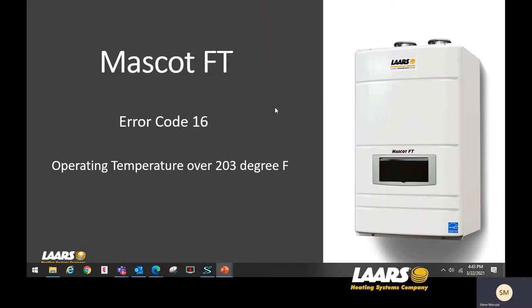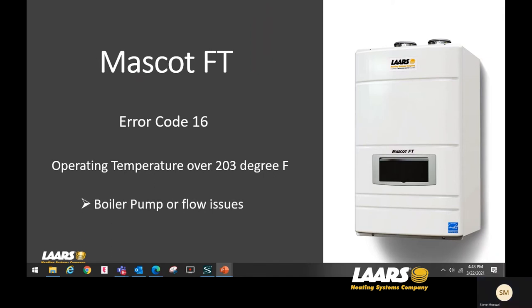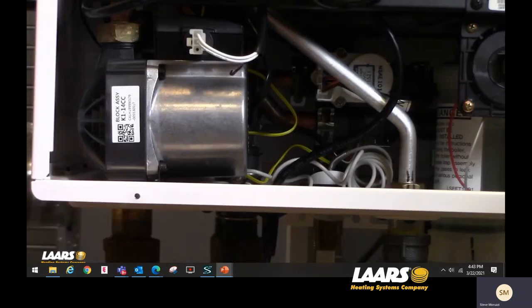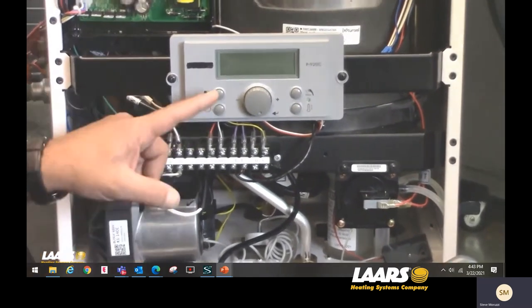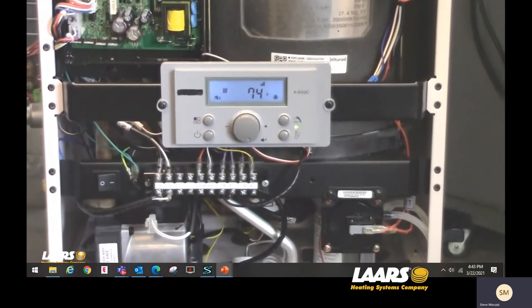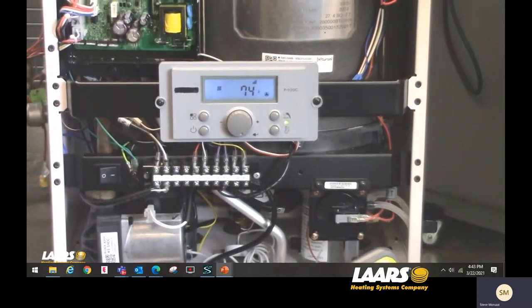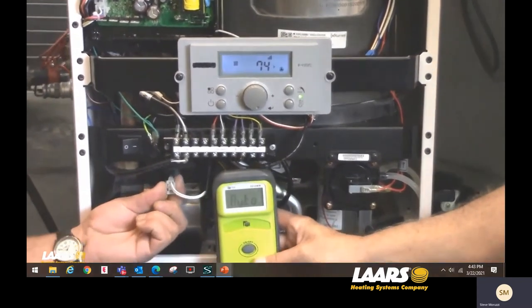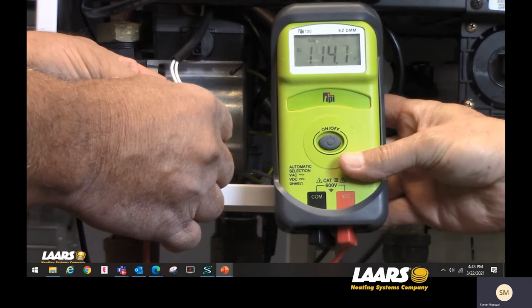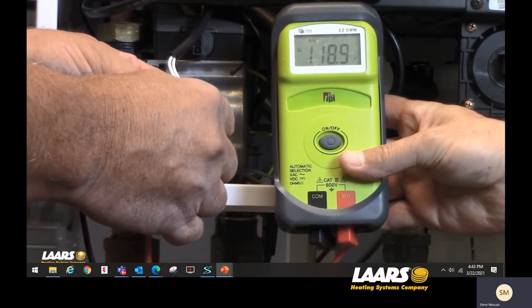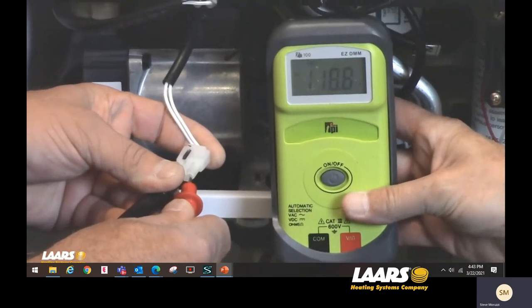Next, we'll talk about error code 16, which is operating temperatures above 203 degrees Fahrenheit. This is about pump flow or flow-related issues, so we're going to talk about checking and testing the pump. Here we're showing the pump location on a Mascot FT Combi 140. First, make sure power is on the boiler and give yourself a call for heat. With a call for heat, measure 120 volts at the molex plug — here you can see we have roughly 118 volts, so we have power going to the pump.